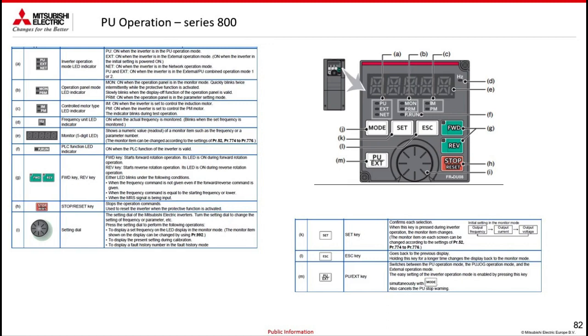if we have an induction motor, then asynchronous, we have the IM LED on. Instead, if we have PM motors, we have the PM LED on. The run LED has disappeared because it has been incorporated into the buttons, and now there is the possibility to drive forward and reverse. So no longer just the green run button that gave a single direction, but I can do forward and reverse, where the LED run is already incorporated.